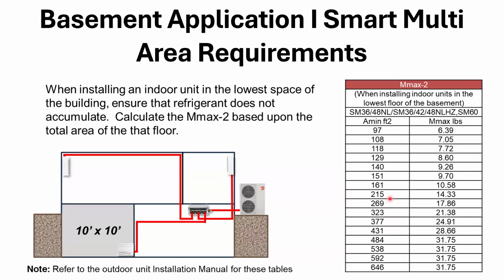So yeah, each system will have a chart found in the outdoor service manual to determine if the system can be installed. You've got to measure that room, know the square footage. And the example is 10 by 10 right here. So for 10 by 10 square footage, it would say the maximum amount of refrigerant for this particular system can only be 7 pounds in this scenario.